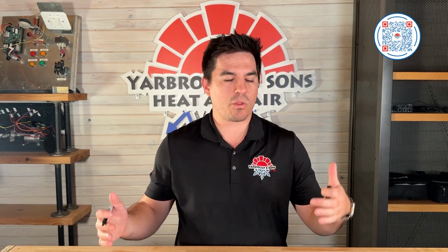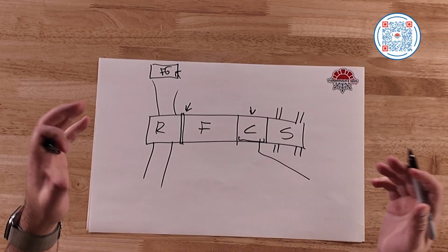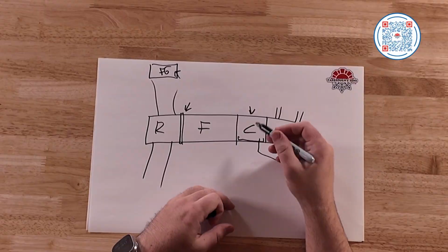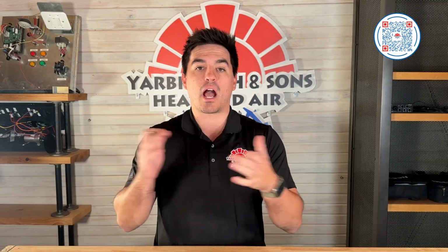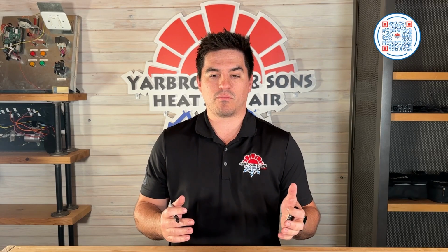Now, you may be experiencing, well, back in the day it didn't seem to be as much of a problem, but now it seems to be an issue. Why is that? Well, due to new refrigerants and new regulations, evaporator coils changed from copper to aluminum. Aluminum doesn't have the same properties that copper does, and it doesn't react with the water in the same way, where it was kind of beneficial. Copper, for whatever reason, helps keep the water more clear.